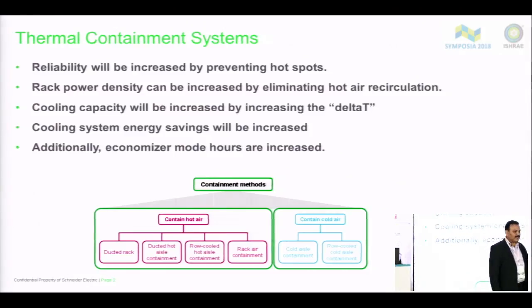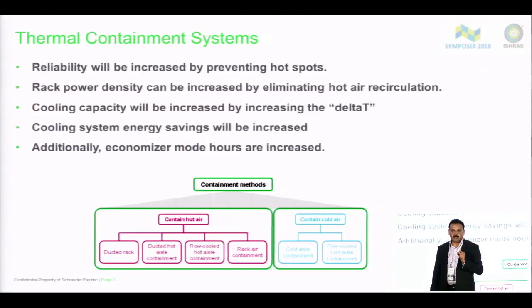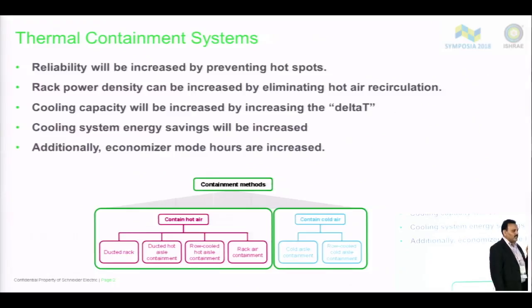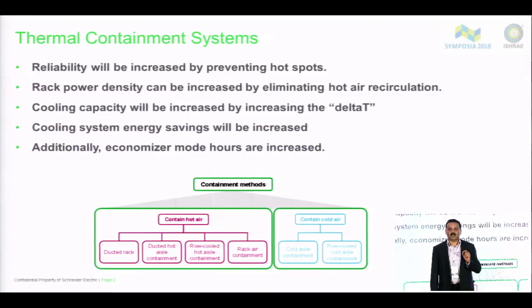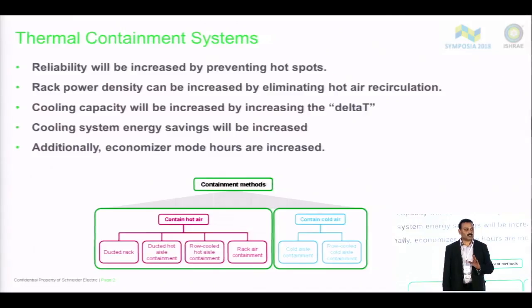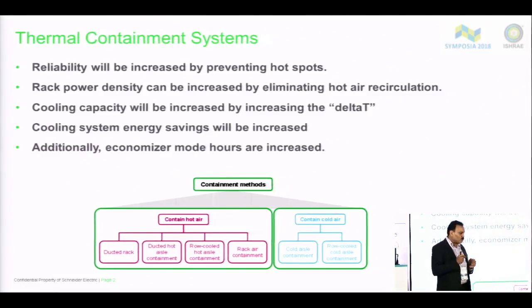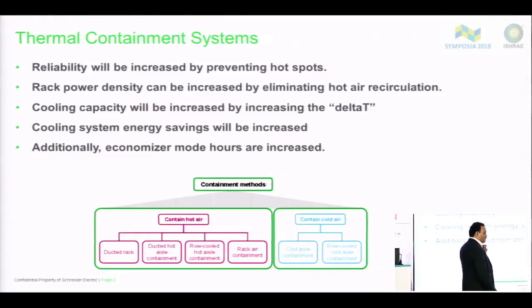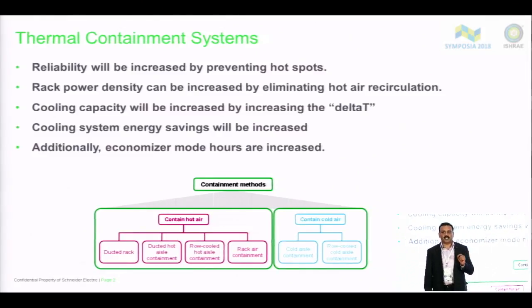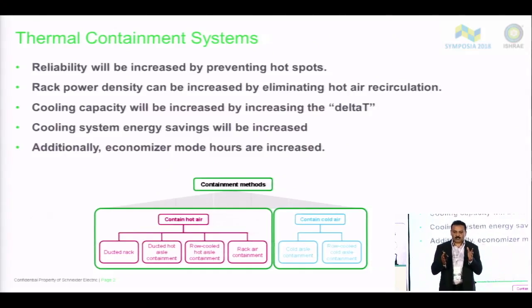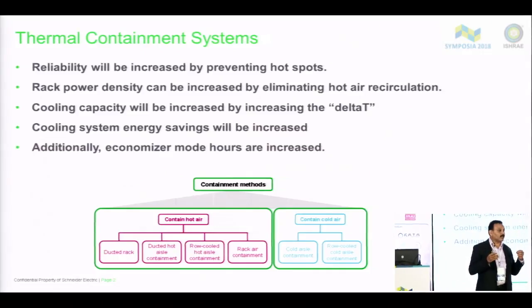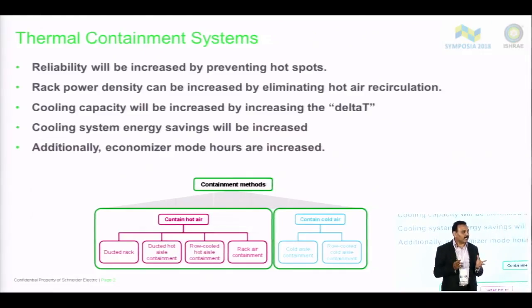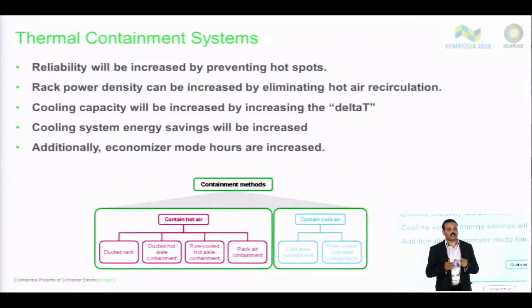But if the same thing is contained, it has been observed by industry analysts, as well as by customers and vendors, that it is possible to revive and increase the cooling capacity by a quarter. Close to 20 to 25% of cooling capacity can be gained just by shifting to a proper containment system on the data center floor. It also gives you an opportunity to increase energy savings just by a simple segregation of hot and cold air. It has been so prevalent in the industry that from this morning almost everyone spoke about containment systems.